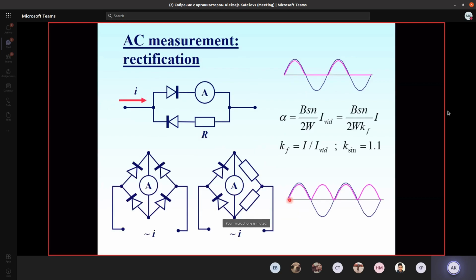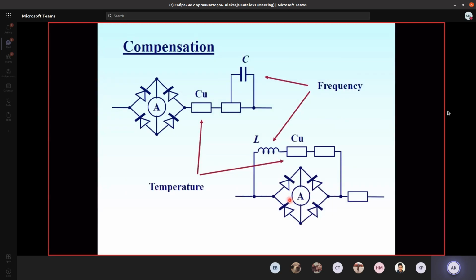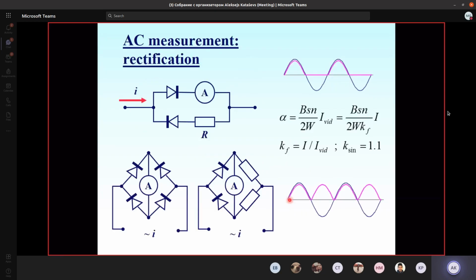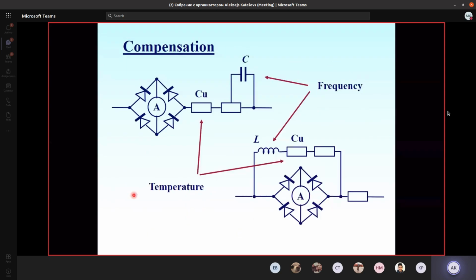Another aspect to consider, especially for high accuracy devices, is that we need to compensate rectifiers for temperature and frequency, because diodes behave very poorly at high frequency. When the frequency is high, the diodes start to pass current in the reciprocal direction, starting to operate as capacitors, and part of the current could go in the opposite direction. Due to this, the current flowing through the ammeter decreases.